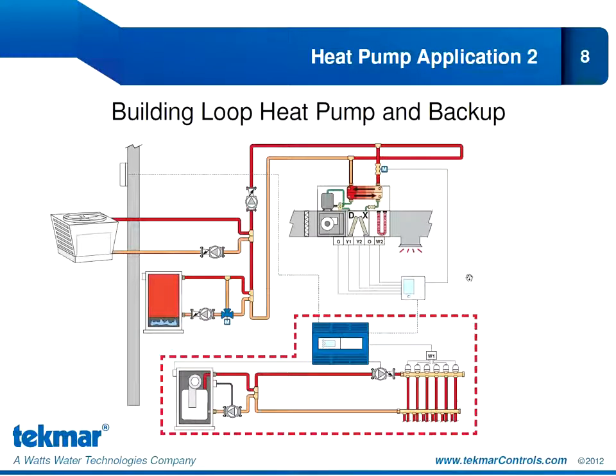Our second heat pump application shows the building loop. So this is a closed water building loop. The loop is maintained within a certain temperature range, typically around 70 degrees Fahrenheit, and that's done with a boiler and a cooling tower. In each unit of the building, we would find a water-to-air heat pump. And this type of configuration is perfect for commercial applications like office buildings, apartment buildings, and hotel applications.